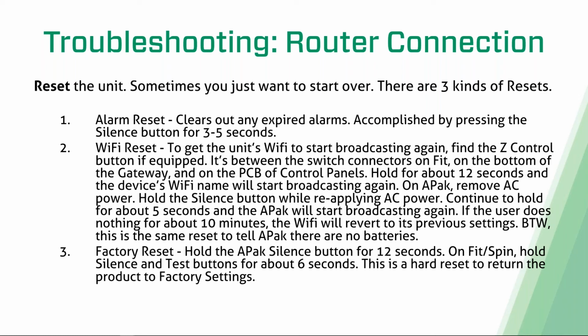A little note on the Wi-Fi, if the user does nothing for about 10 minutes on the APak, the Wi-Fi does revert to its previous settings. So it's expecting that you want to rebroadcast the Wi-Fi, but if you don't connect to it, it's going to go, okay, that must have been a mistake, and it's just going to revert to what it was. And sometimes their APak is giving them a beep because there's no batteries, and they want to tell the APak, hey, there are no batteries, quit alarming me for that reason. That's the same reset you would do for that, just as an FYI. Not related to this webinar really, but just a little side note.